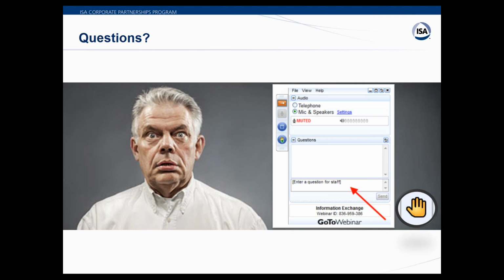Yeah, hysteresis to me is memory. So as you flex something or change something on a sensor, it retains memory whether you're going up or coming down. So in the case of pressure or a gauge, as the fellow that asked the question, as you push it to its maximum, as you come back, it tends to stay towards the 100% that you stressed it to, as opposed to when you're coming up, it kind of tends to lean towards the 0%. So whether you're going up or coming down, you might see hysteresis. Today's instruments really are so much better, the way they can handle that. So hysteresis is not as big a factor.